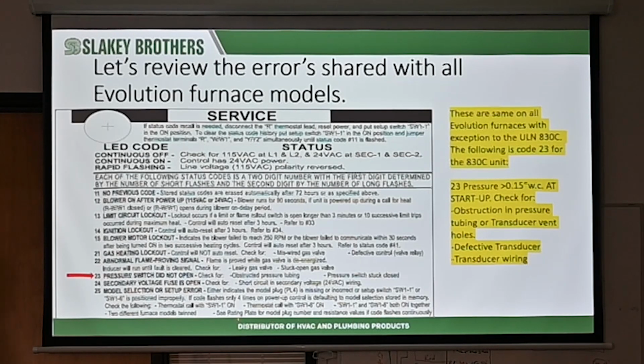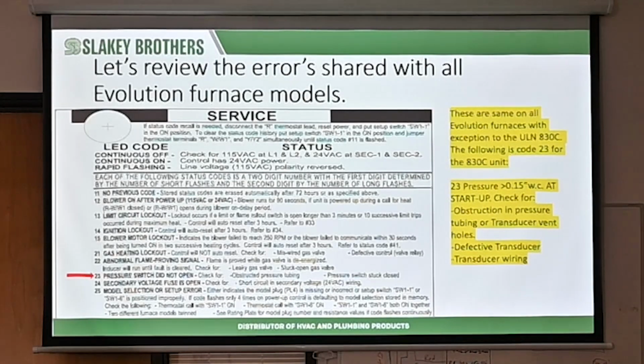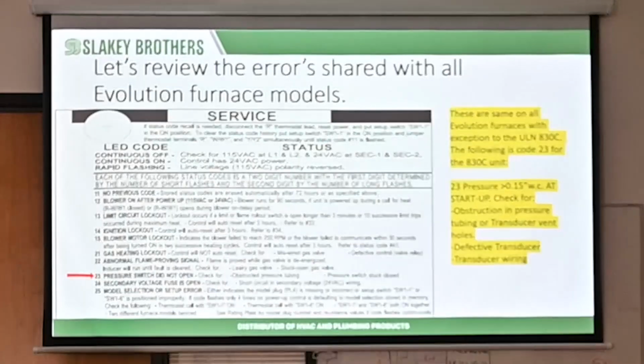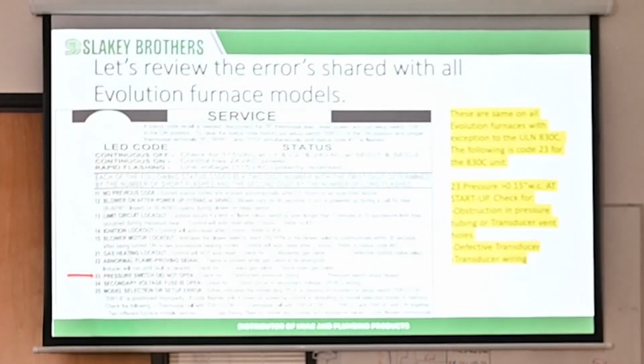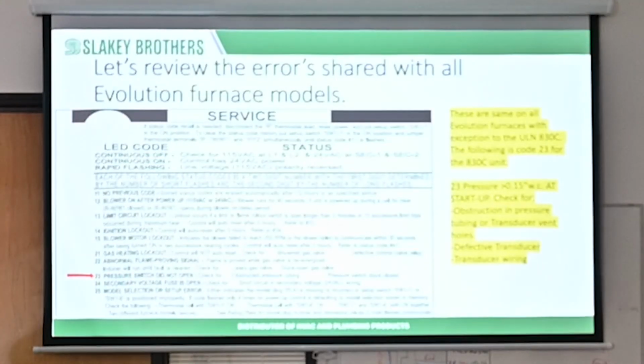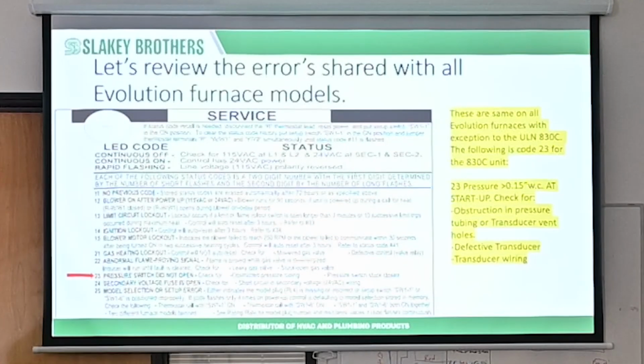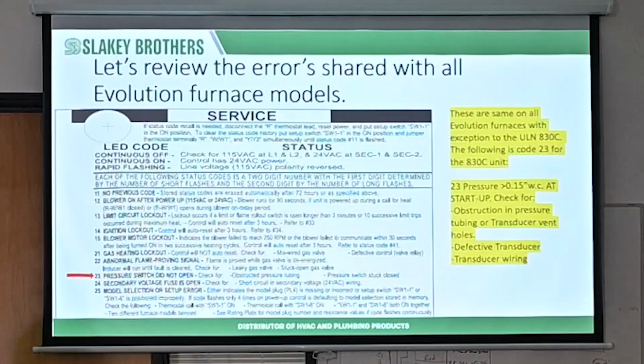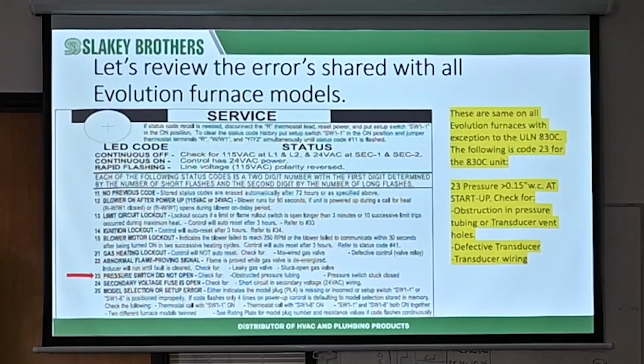Now, the other reason is this right here. SW1 number 6. On a furnace, SW1 number 6 is on, or SW1 number 1 is on. If you're looking for past error codes, you flip it on and look for error codes. As soon as you do that, flip it off. If you leave it on and then ask for heat, you're going to get a 25. You've got to make sure number 1 stays off after you look up your error code.